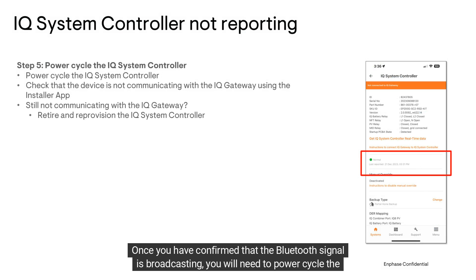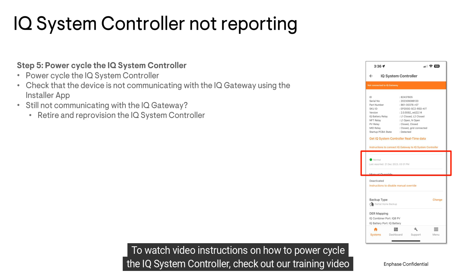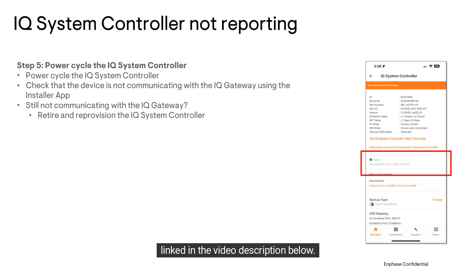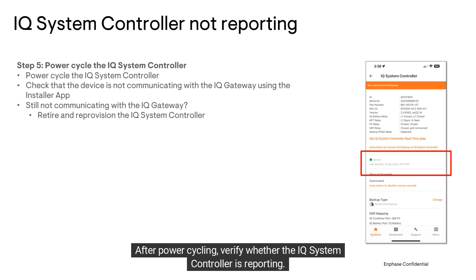Once you have confirmed that the Bluetooth signal is broadcasting, you will need to power cycle the IQ system controller. To watch video instructions on how to power cycle the IQ system controller, check out our training video linked in the video description below. After power cycling, verify whether the IQ system controller is reporting.